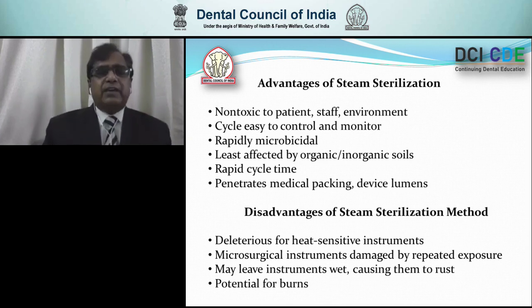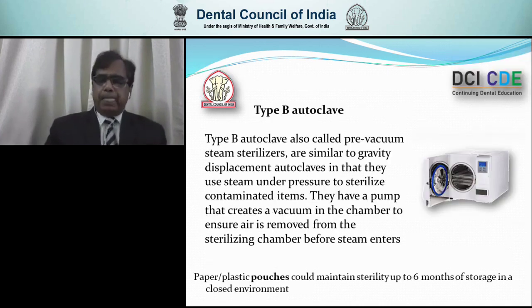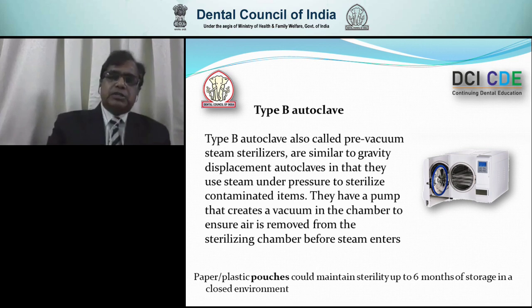Type B autoclaves come with the added advantage of a pre-vacuum cycle, so all the instruments will come out dry. Another advantage of the type B autoclave is that there are different cycles, so you can choose your cycle according to the instruments you are sterilizing. If you are using paper and plastic pouches, the instruments remain sterile for up to six months, so they need not be sterilized again and again once sterilized.